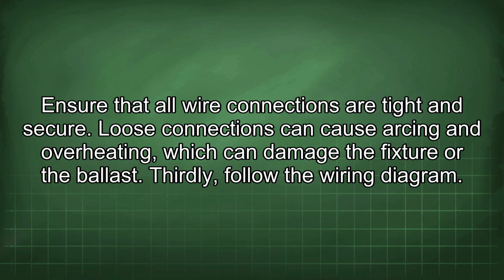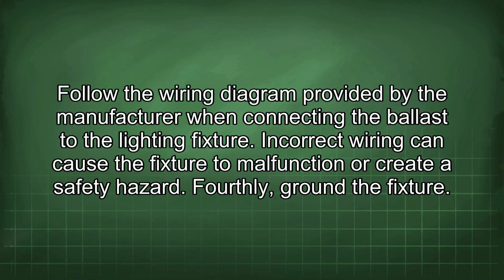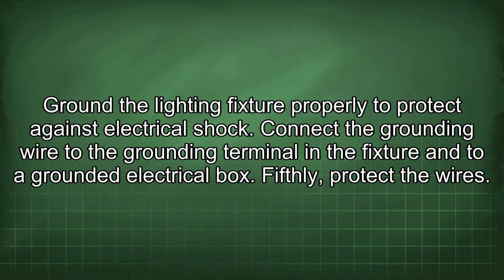Thirdly, follow the wiring diagram. Follow the wiring diagram provided by the manufacturer when connecting the ballast to the lighting fixture. Incorrect wiring can cause the fixture to malfunction or create a safety hazard. Fourthly, ground the fixture. Ground the lighting fixture properly to protect against electrical shock. Connect the grounding wire to the grounding terminal in the fixture and to a grounded electrical box.